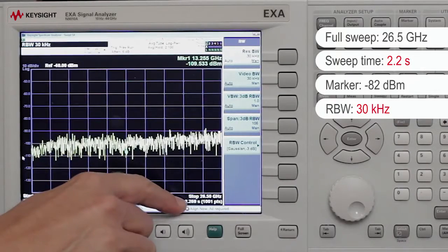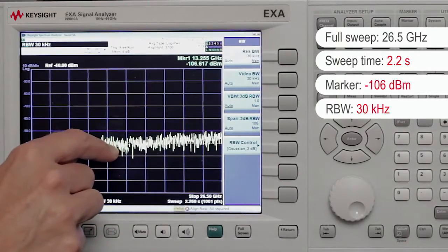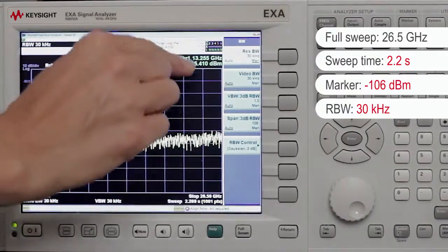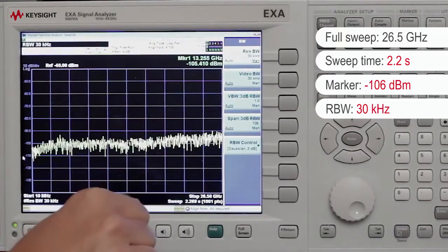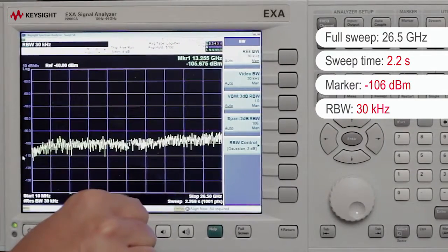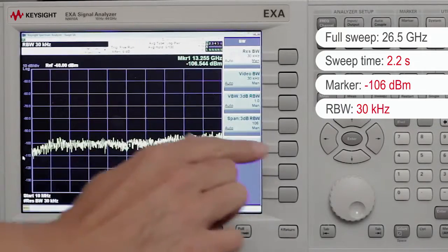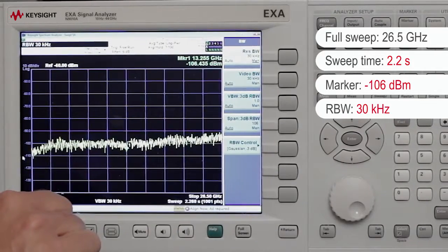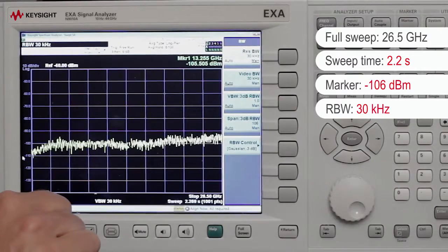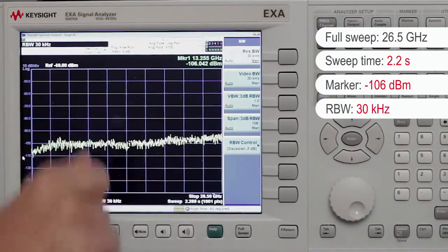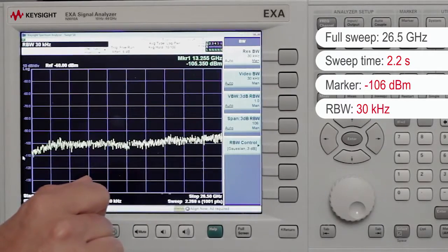Notice that our sweep time is now 2.2 seconds and our marker one reading is at minus 106 dBm. With the EXA's new fast sweep capability, we're able to still quickly sweep this full span with our lower resolution bandwidth settings. On older analyzers, when you reduce the resolution bandwidth settings, the sweep speed was reduced much more dramatically.